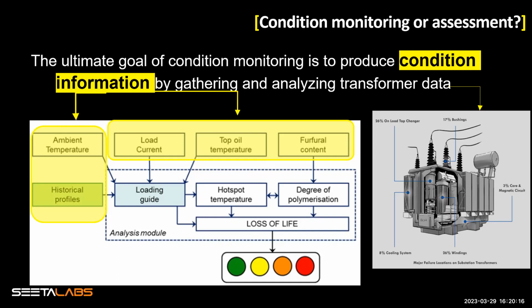There are multiple spots inside a transformer prone to failures. The most important zones are the tap changers and windings. The winding in particular is one of the most critical places because it's not accessible at all times. Every time you have a fault in a winding, or identify with some confidence that there's a fault there, you have to make a reasonable techno-economical explanation to your asset manager. This is what happens in industry.